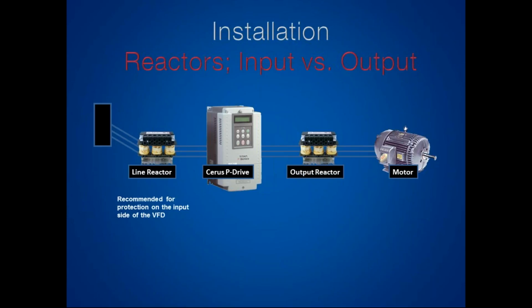One thing to also kind of keep in mind, and I can't remember if I even made a slide about this or not, but when we're talking about line reactors, you may have also heard the term DC link reactor or DC bus choke. So the DC link reactor and the DC bus choke are installed after those diodes in your drive. So they're installed about halfway through your drive. Okay? The problem with this is that you're leaving those diodes and that rectifier bridge, the whole front part of your drive, being left unprotected. So those are still subject to the harm that harmonics can do.